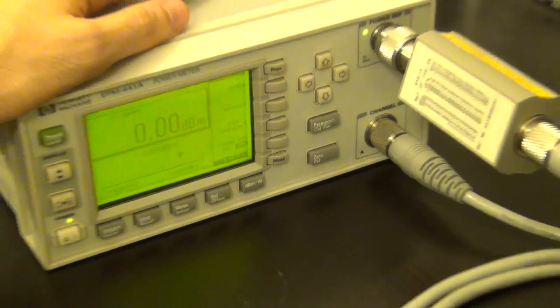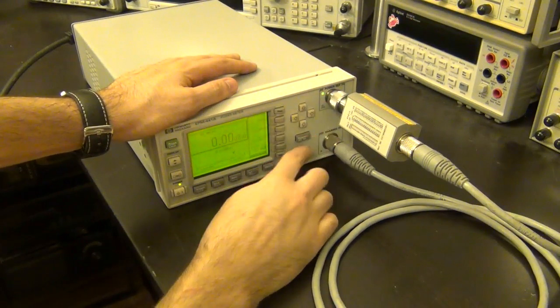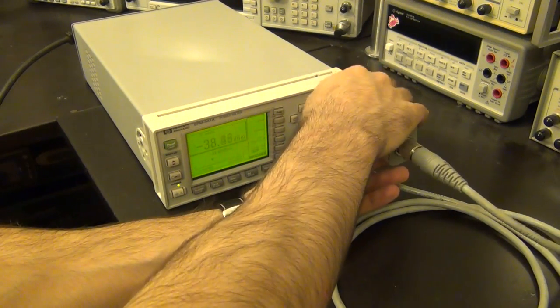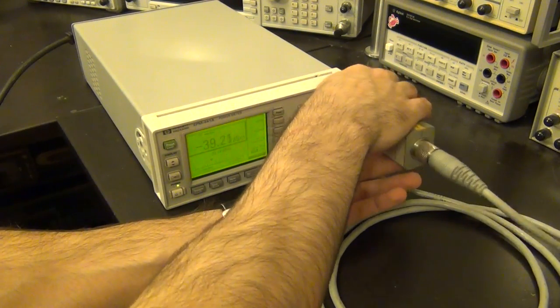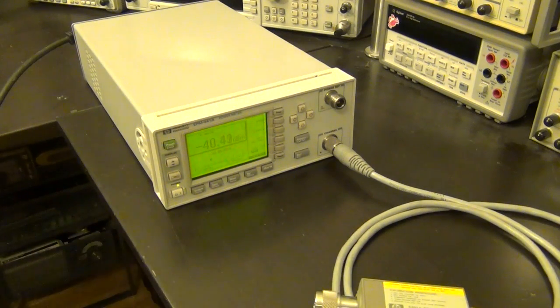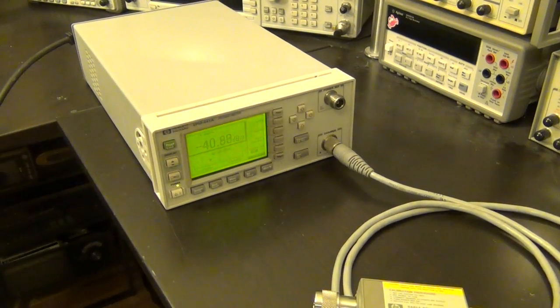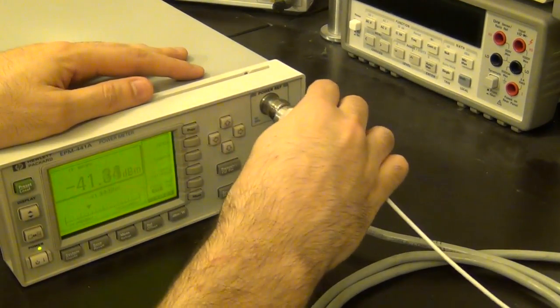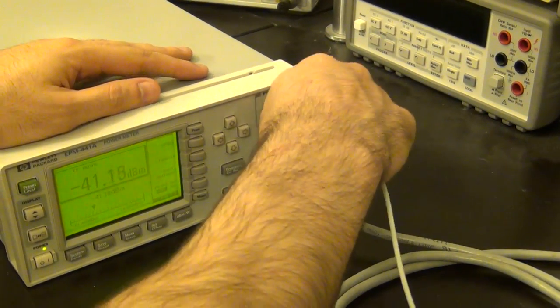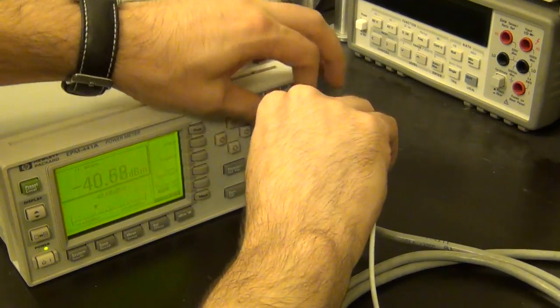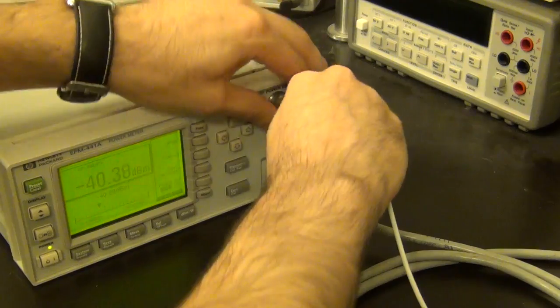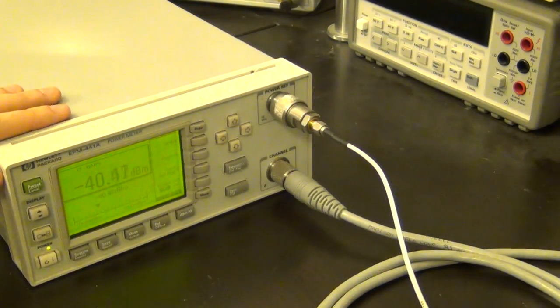So two things I want to check. I want to first check to see if this signal is at 50 megahertz, because it should be very close, and because 50 megahertz is the calibration point of all the sensors. That's the standard reference calibration frequency, so that's one thing we're going to make sure. In order to do that, I have it connected here to my universal counter, which I've used in some of my other videos, and the counter should be fairly well calibrated. Here we go.